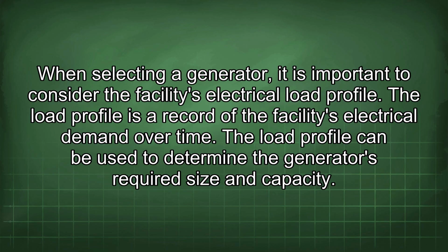When selecting a generator, it is important to consider the facility's electrical load profile. The load profile is a record of the facility's electrical demand over time. The load profile can be used to determine the generator's required size and capacity.